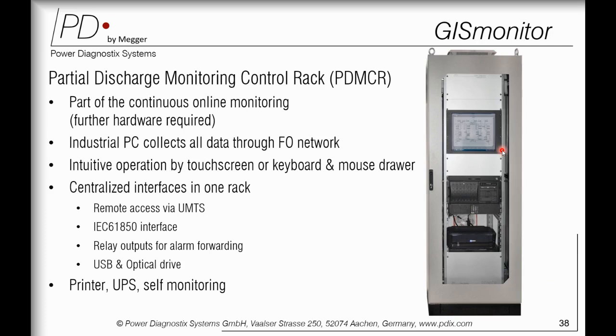And the main is the controlling rack, or we can say the partial discharge monitoring control rack, PDMCR. It is a part of the continuous online PD monitoring system. It has a completely industrial PC that collects all data through the fiber optics network, which is connected between the acquisition rack and the outdoor rack. It has a completely inbuilt PC with touch screen, with mouse and keyboard, to see the drawings or the layout, because it's a completely centralized interface with one rack, with remote access, IEC 61850 interface, relay output for alarm forward, USB and optical drive, along with UPS, printer, and a self-monitoring solution with the system.